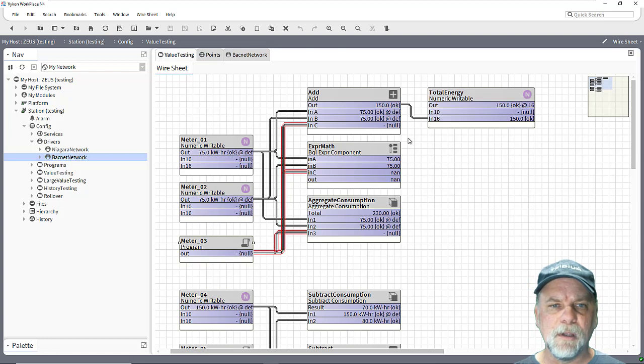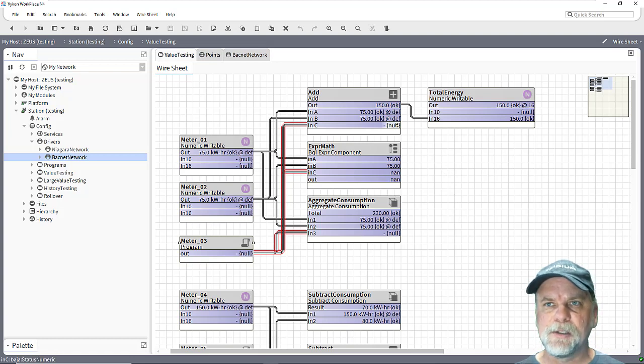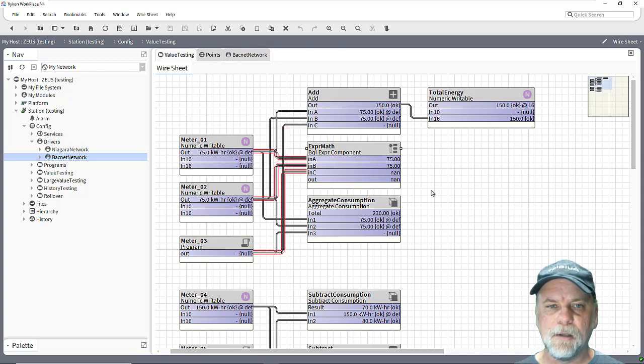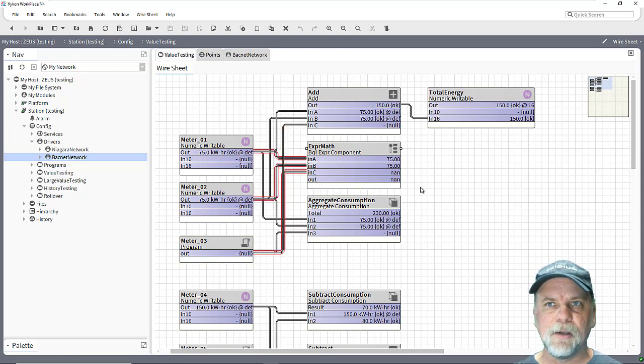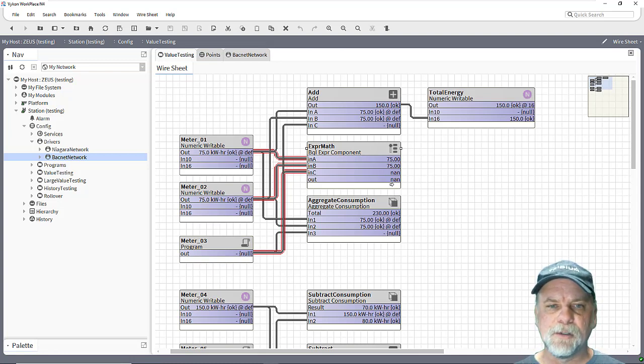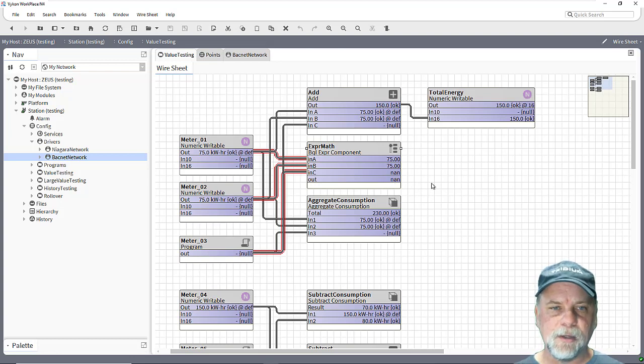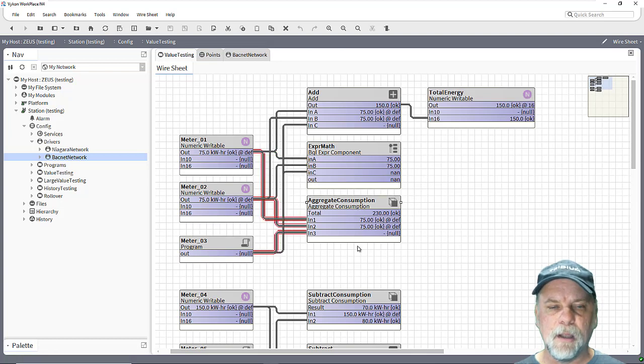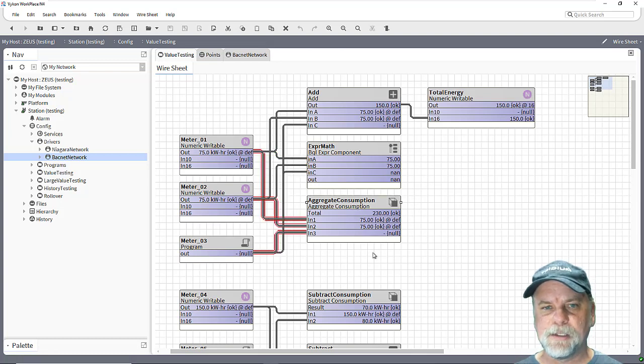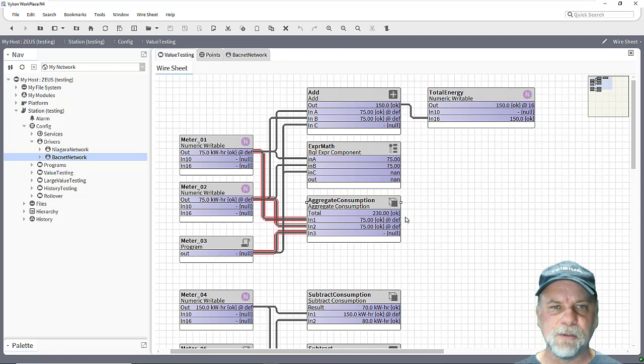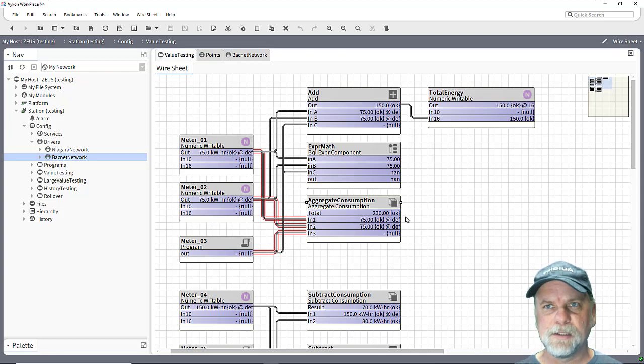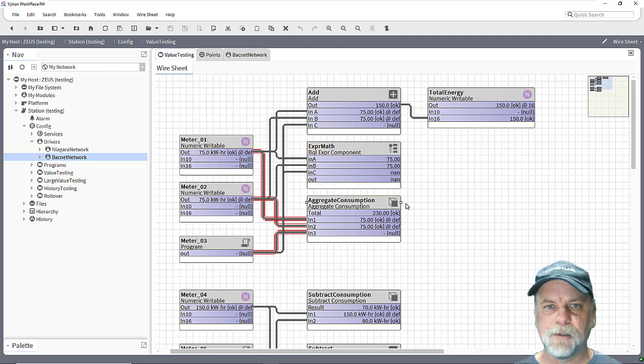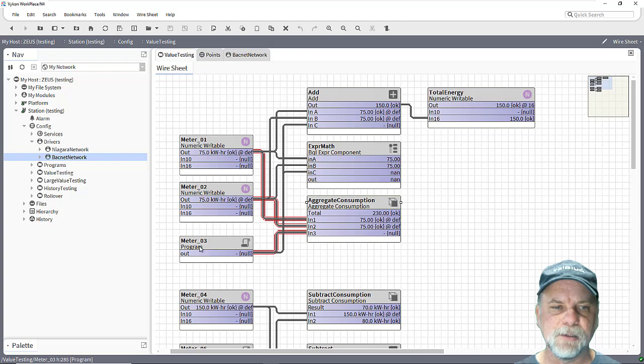So for example if I have a null status that can also impact your control logic. So with a null status on the input of the add block it also ignores that input and the output goes to 150. The expression math unfortunately treats that null status on the input as not a number and NaN, which results in a NaN output value on the calculation as well. And the aggregate consumption block again handles the case where you have a null status and it just uses that last known value. So we don't see a drop in our totalized consumption value which we don't want to see because that would introduce an anomaly in our analytics or possibly in our control logic as well.